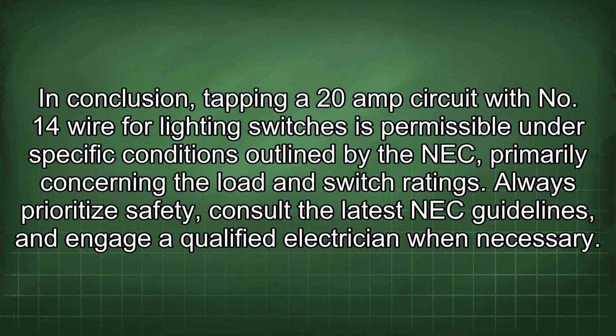In conclusion, tapping a 20 amp circuit with 14 wire for lighting switches is permissible under specific conditions outlined by the NEC, primarily concerning the load and switch ratings. Always prioritize safety, consult the latest NEC guidelines, and engage a qualified electrician when necessary.